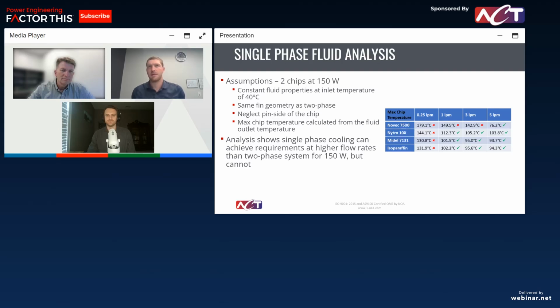Yeah, I can take that one. Really, it comes down to pressure drop and gravity head. So depending on your orientation, like I said, you have to have that condenser above your evaporator, and depending on what cooling you need and what flow rate you need, sometimes you need a greater height difference than in other situations. We've had ones where we only needed less than a foot between our evaporator and our condenser over a 24-foot span between them horizontally.